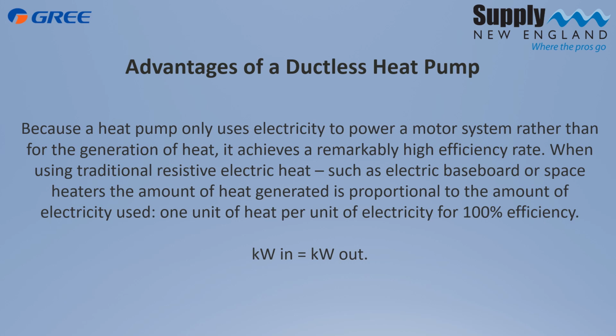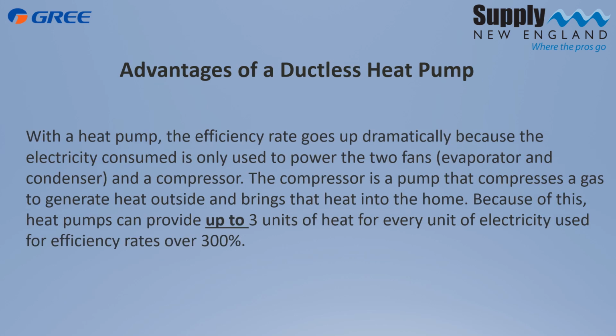kW. Electric heat is considered to be 100% efficient. You pay for 1 kW of electricity, you get 1 kW of heat. 100% efficient. On a mini split, however, it could be 3 times as much of that. You could pay for 1 kW of electricity and get 3 kWs of heat out of that. The key to remember, guys, is I said up to. Make sure you're checking your submittals on the equipment that you're installing to know exactly what you're going to get there.